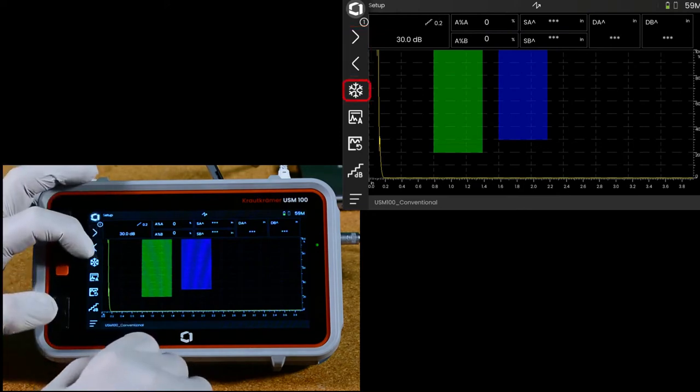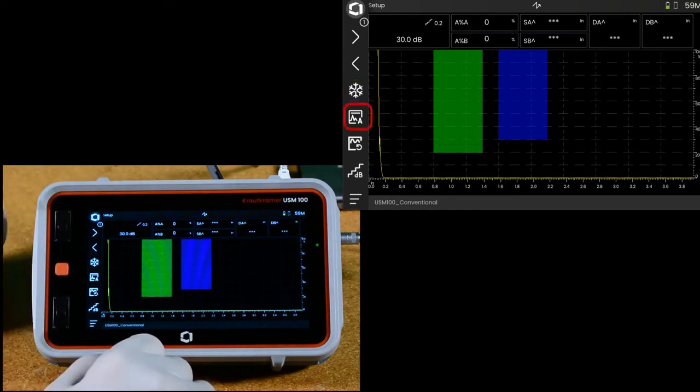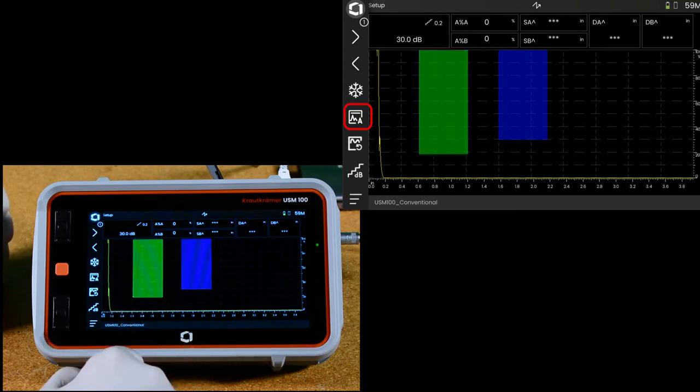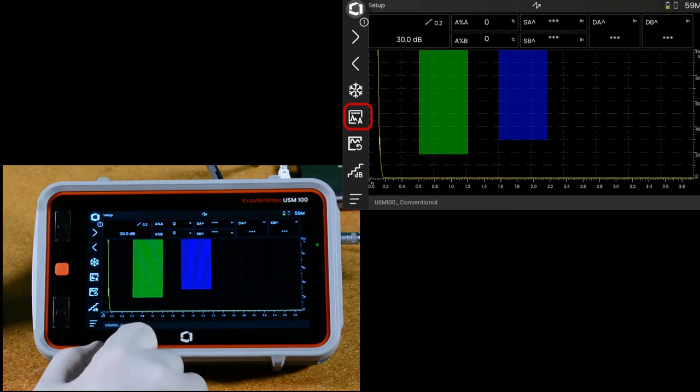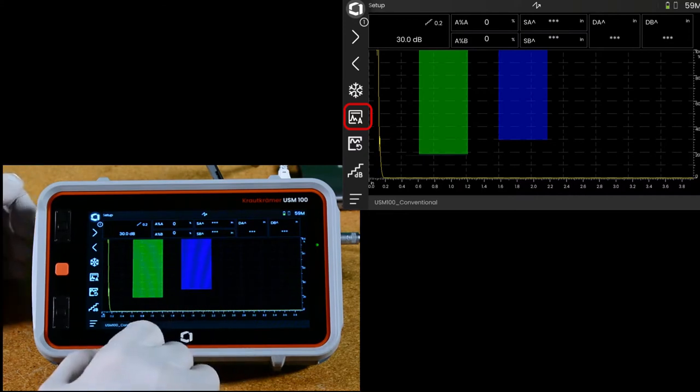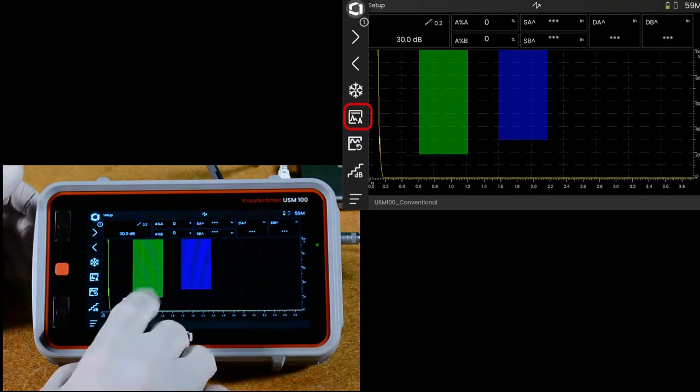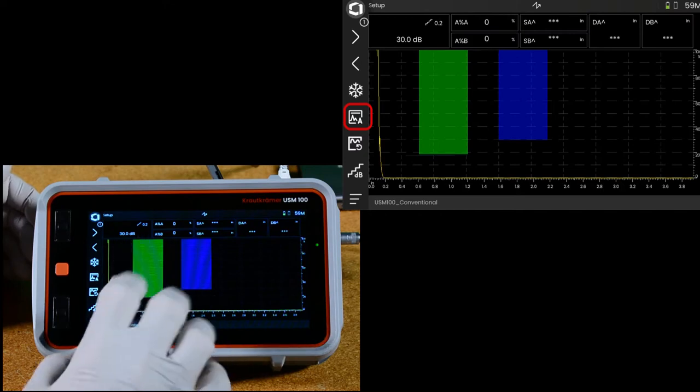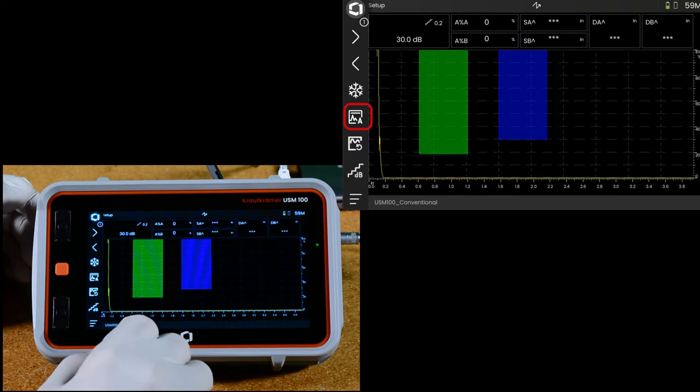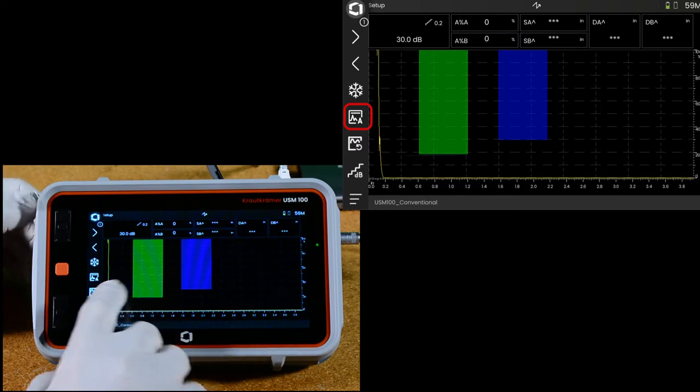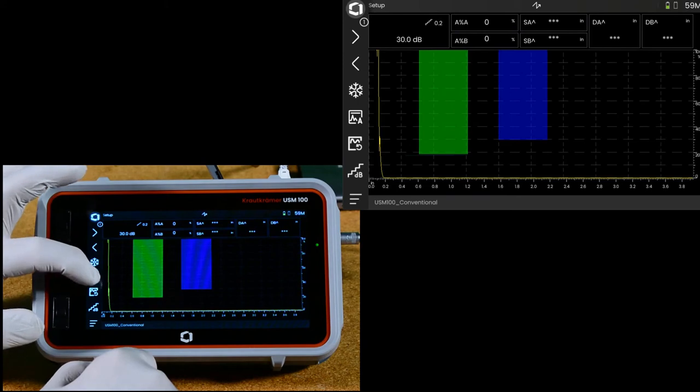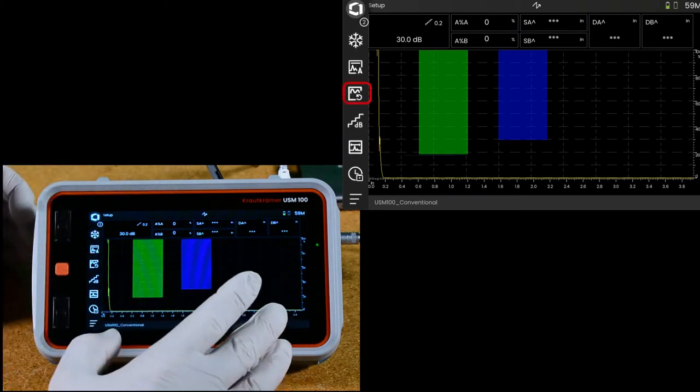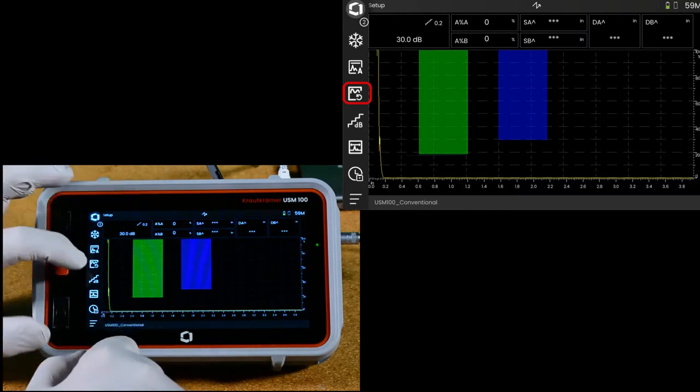Right underneath that is the freeze, the snowflake, and auto-80 is another key feature of this instrument. If you have your gate A over top of a signal, you hit the auto-80 button, it will adjust the gain automatically to make that 80% screen height. It's actually not always 80. You have the choice of choosing a different amplitude that you would like to have the automatic gain control set to. That's on one of the menus we can look at a little bit later. Underneath that is envelope clear. So if you have the envelope mode turned on, you can reset the envelope with that button.